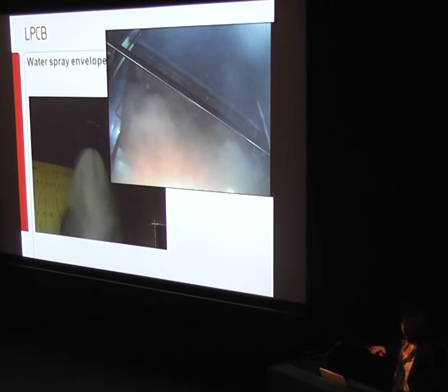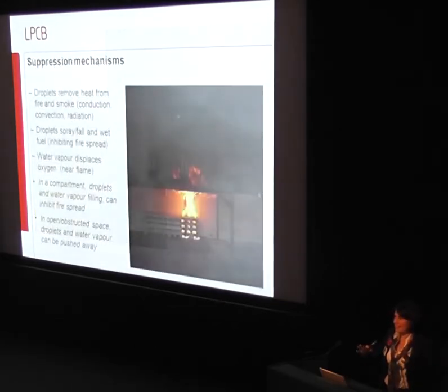So that was a demonstration. I don't know how clear it was, but we were looking up at a ceiling with 4 nozzles on. That's the single nozzle in a compartment, and that's the 4 nozzles. And although you do get the columns of water, you do get a little bit of infill, but some of what you see there is just a visual optical illusion. They were distinct sprays.